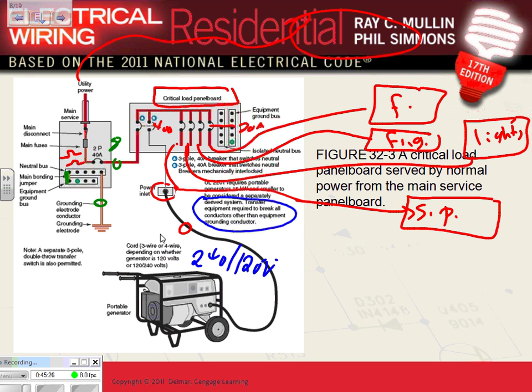So 3-pole, you have to have 3-pole breakers. If it's a separately derived system, you need to be able to switch the neutral. You have to be able to switch the neutral for a separately derived system. So you have to be able to switch a 3-pole breaker right here. You bring your neutral, so you can switch your neutral as well. Okay, so separately derived system, you turn your generator on, you have power. Any questions about this? Separately derived system.